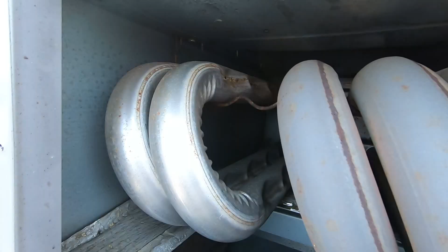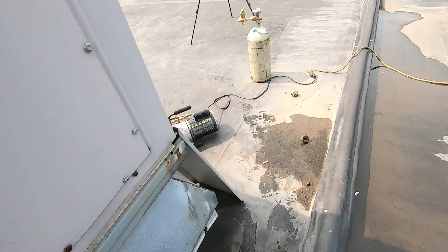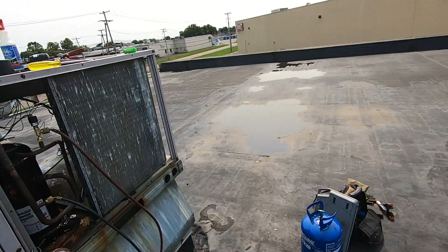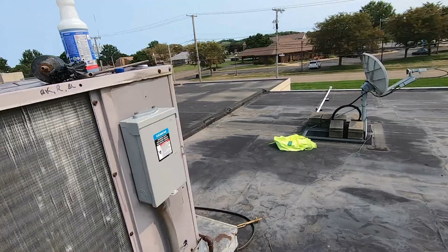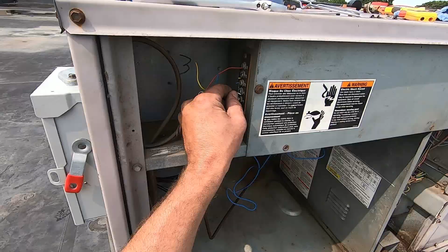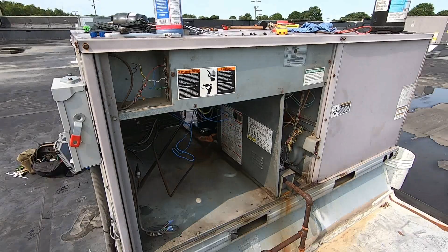You'll get cracks there. But we're gonna go ahead and disable this unit in heat. I have to, you know. You leave a unit in a shape like this running and someone gets sick, they're gonna look back and see who was the last guy there, and it'll be me. I certainly don't want that on my conscience. So gas is off, we're gonna disable the low volt call for heat, and that'll be that. We'll quote them a new heat exchanger.